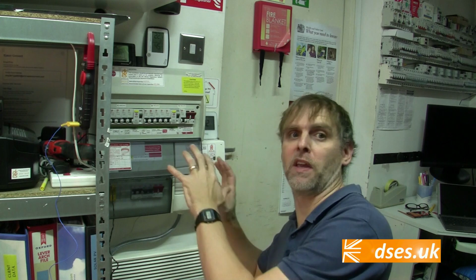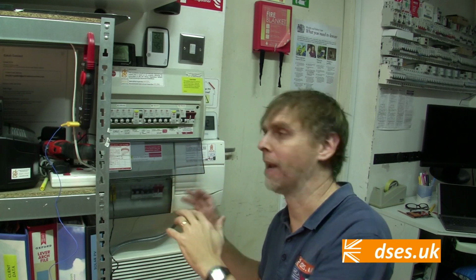Paranoid as I was that they'd haul me up over something, I went through everything in the house to ensure there were no loose connections, no duff numbers, no shoddy workmanship, and that everything tested and added up to the maths. In short, for an installation where arc fault detection is now being installed as a retrofit on an installation others have designed, installed and maintained, or not, over the years, well, this is as good as it gets, and I'm as confident as I can be that this remains about tip-top for its time.